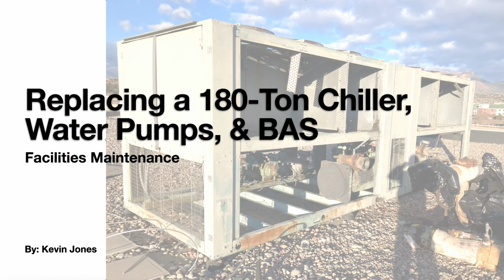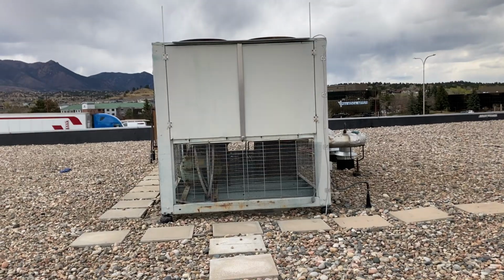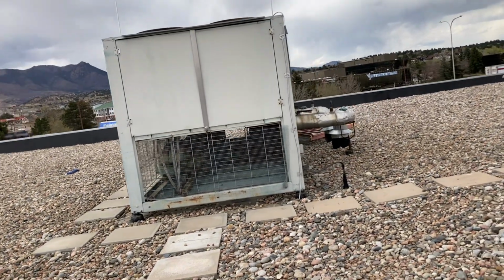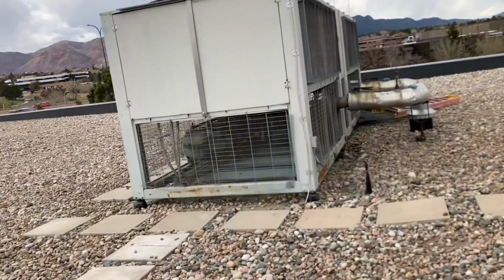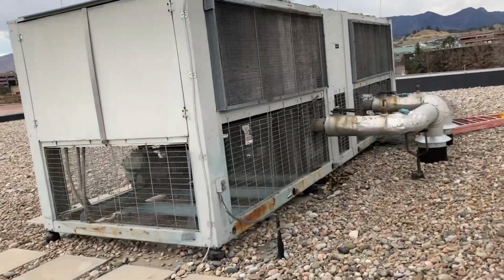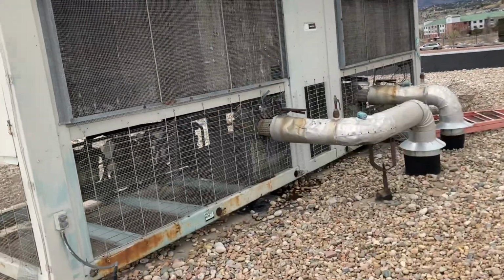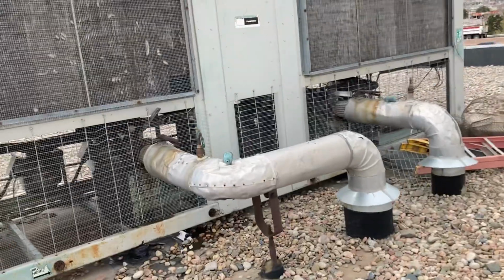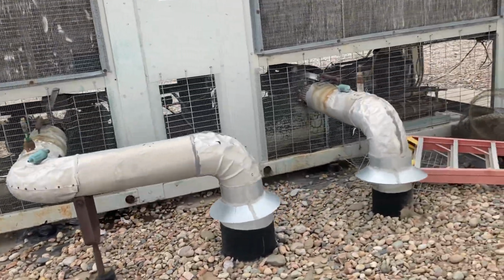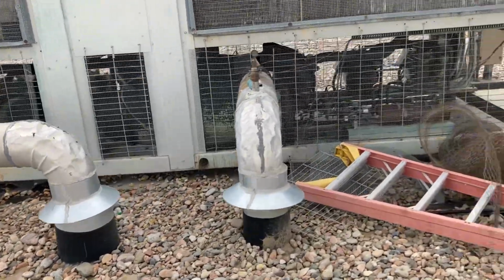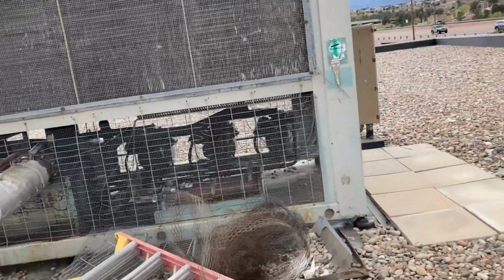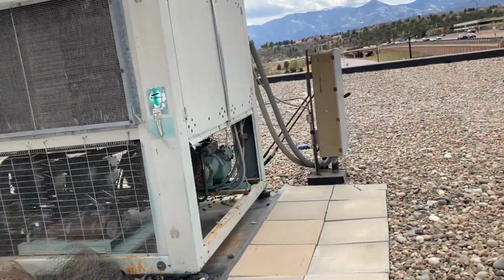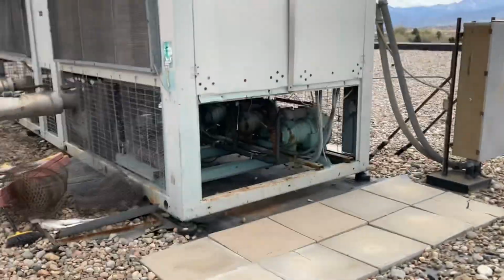Okay, today we are replacing a 180-ton chiller, water pumps, and the BAS on a commercial office building. So here's the old 180-ton Carrier chiller we're going to be replacing. It's 40 years old. You can see it's served its time. The compressors on this unit have been rebuilt over the years. It's become a high maintenance chiller.